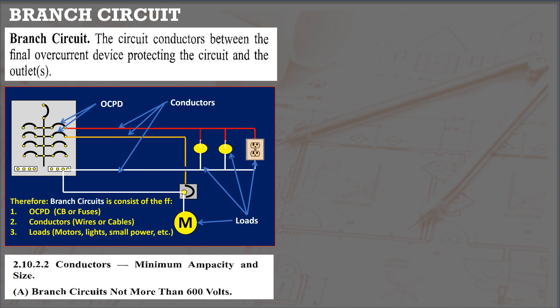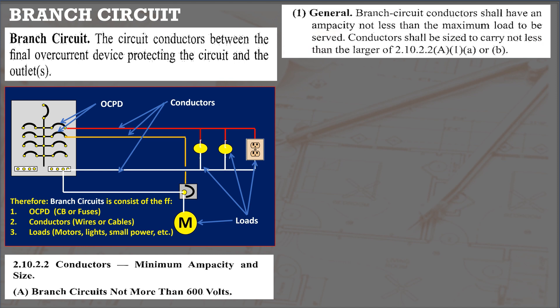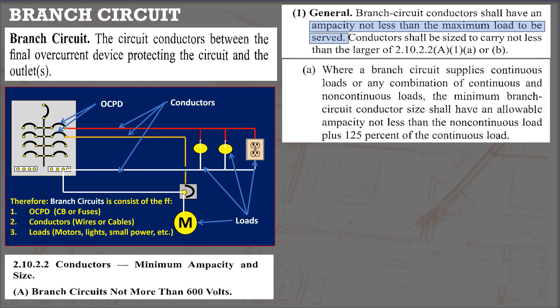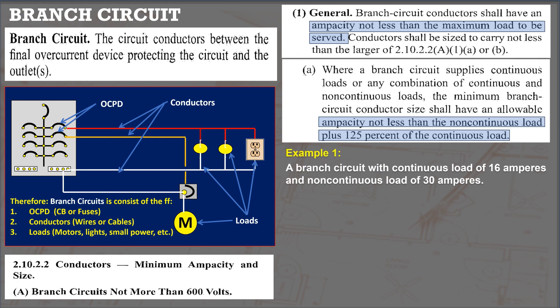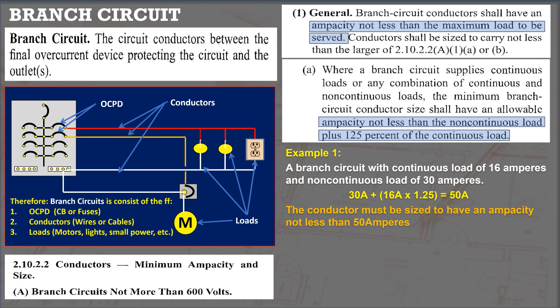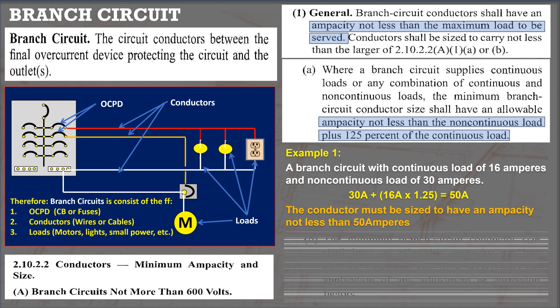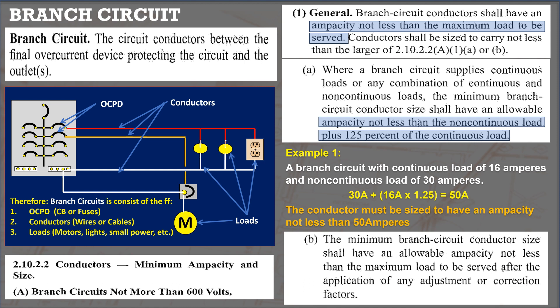How to determine conductor size for branch circuits? In Section 2.10.2.2, the ampacity of a branch circuit conductor must not be less than the maximum load it serves. If carrying a continuous load or a combination of non-continuous and continuous load, the minimum branch circuit conductor shall not be less than the non-continuous load plus 125% of the continuous load. For example, a branch circuit with a continuous load of 16 amperes and a non-continuous load of 30 amperes gives a total of 50 amperes; therefore, the minimum conductor size shall not be less than 50 amperes. We also need to consider adjustment and correction factors.